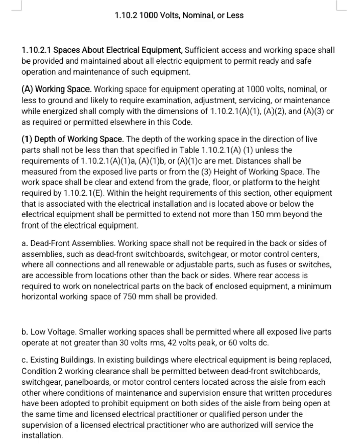1. Depth of working space. The depth of the working space in the direction of live parts shall not be less than specified in Table 1.10.2.1 A1 unless the requirements of 1.10.2.1 A1A, A1B, or A1C are met. Distances shall be measured from the exposed live parts or from the enclosure or opening if the live parts are enclosed.